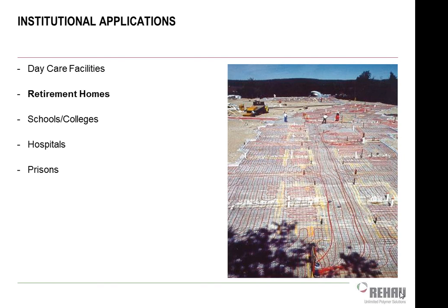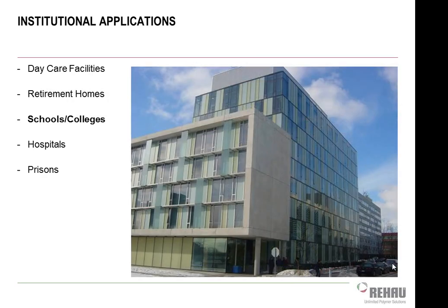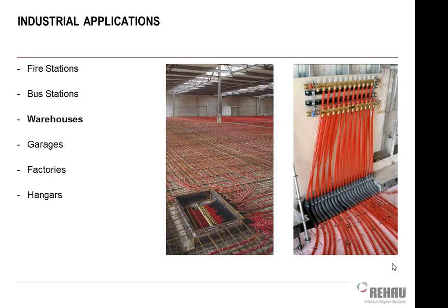And then prisons are extremely popular for radiant, and that's because we're very concerned with keeping prisoners happy. No, actually, it is because of that, I suppose. Unhappy prisoners tend to lead to rioting prisoners. But the real reason is if we put airside systems in prisons, or at least larger airside systems, that tends to be something people can tamper with and probably make weapons out of. Whereas if you put radiant tubing in a floor, it's kind of hard to get the tubing out of the ground at that point. So it's more tamper-proof, if you will. So that's some of those applications.